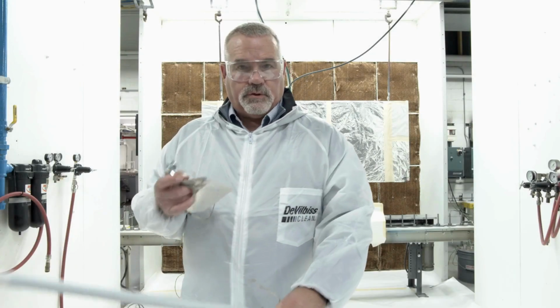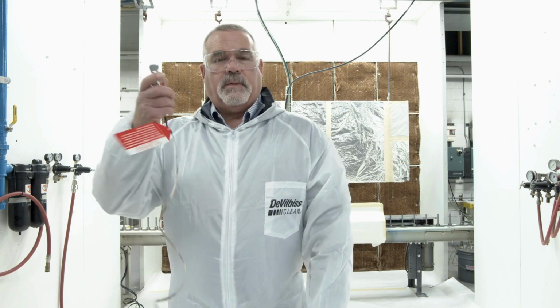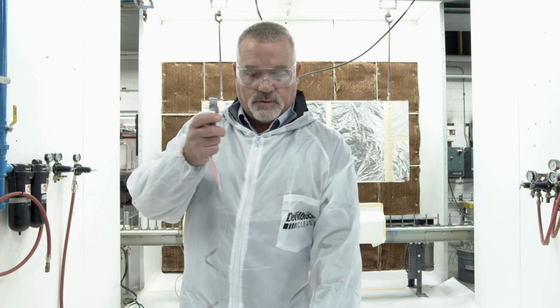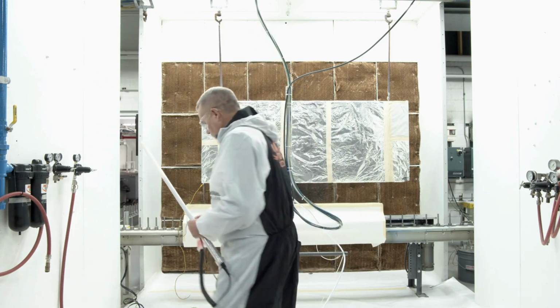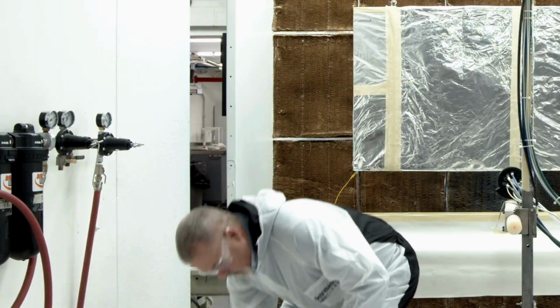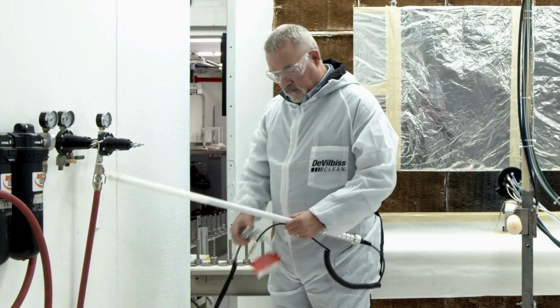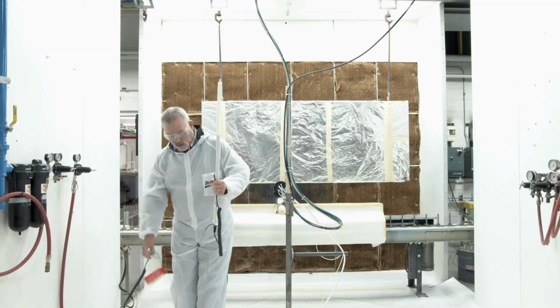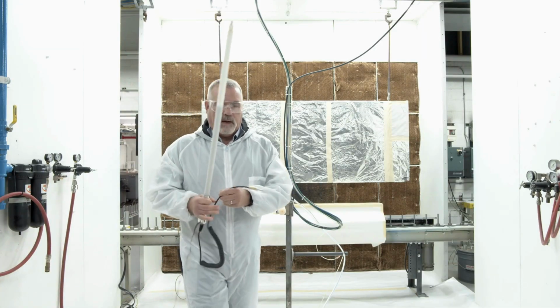I'm going to talk about the high voltage probe. First thing you want to do is make sure that you have this connected to true earth ground. I have a true earth ground right over here that I'm going to connect to. If you don't connect it to true earth ground, you're not going to get the readings be proper.